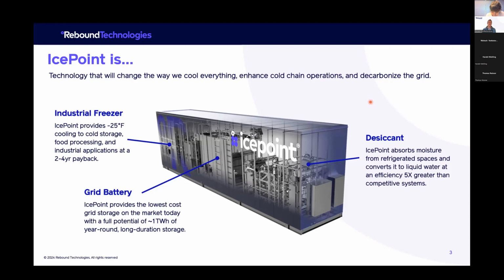Not only is this important for product quality, but for worker safety and efficiency. We can come in and simultaneously cool and dry their air, and we do that at a much higher efficiency than traditional desiccant systems. First, the scale of our technology is much higher because our refrigerant is water. We're already processing so much water that processing a bit more, we can do much more efficiently. And secondly, we're not over-drying the air or over-concentrating our brine.